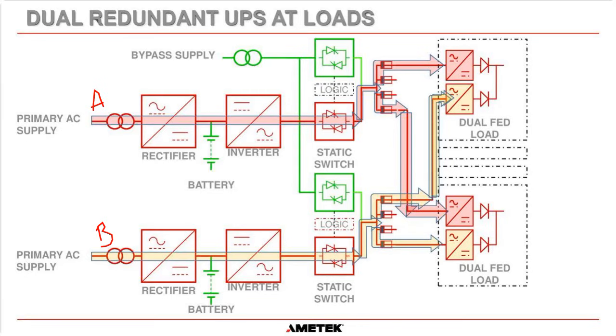What happens is each UPS feeds into a power supply, an AC to DC power supply. This one here is fed from UPS A, and this one here, if you follow it down, is fed from UPS B. Because it's much easier to parallel DC than it is to parallel AC, the power supplies have DC outputs, and they are diode ORed together on the output here. So really, in truth, they're running in parallel with each other.